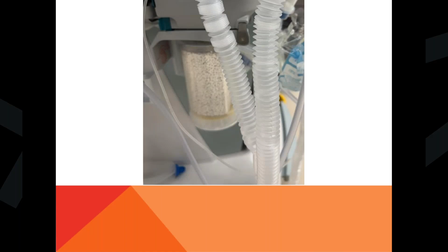So a huge part of the patient circuit that's kind of ignored or overlooked, especially during troubleshooting, is your scavenger slash waste anesthesia gas, depending on where you work and what they want to call it. So basically what the scavenger does, it's a vacuum circuit that pulls the waste anesthesia, exhaled anesthesia gas, and the CO2 from the patient breathing circuit. The one big thing is that it keeps the waste anesthesia gas from being released in the room, like my little vaporizer problem did.